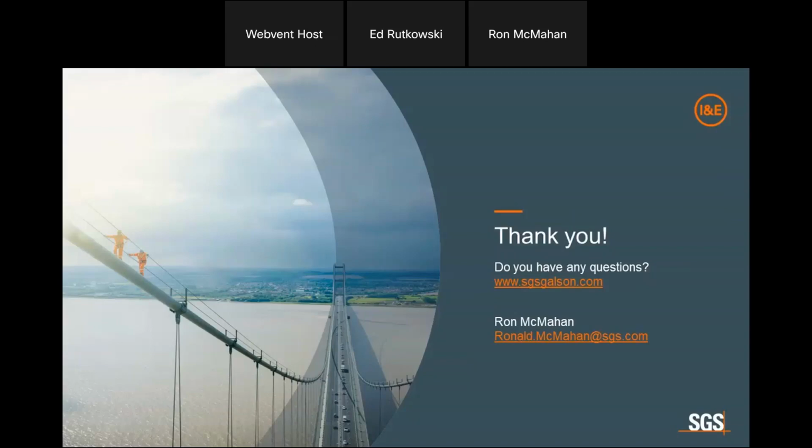Okay, thanks. There's a question from Luis who asks, are there any reliable software or applications to document calibration equipment and keep records current? So our LiveView system has the ability of storing documentation against locations, and that's one of the things we're moving toward. Some of that involves 3D modeling for a facility, so you can tag exactly what's going on. You could have a little window to the side that says calibrated instruments, reference instruments, all those kinds of things, and you could keep track of it by taking a PDF or any kind of document format and attaching it to a geotag location.